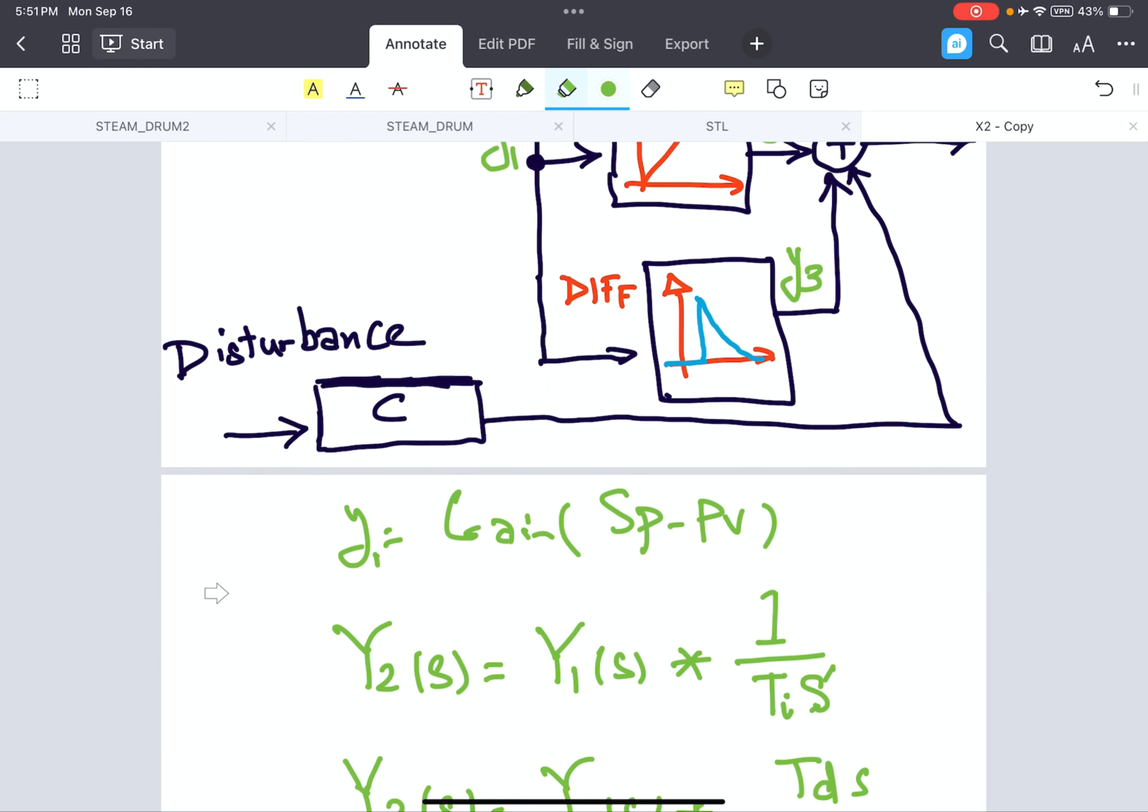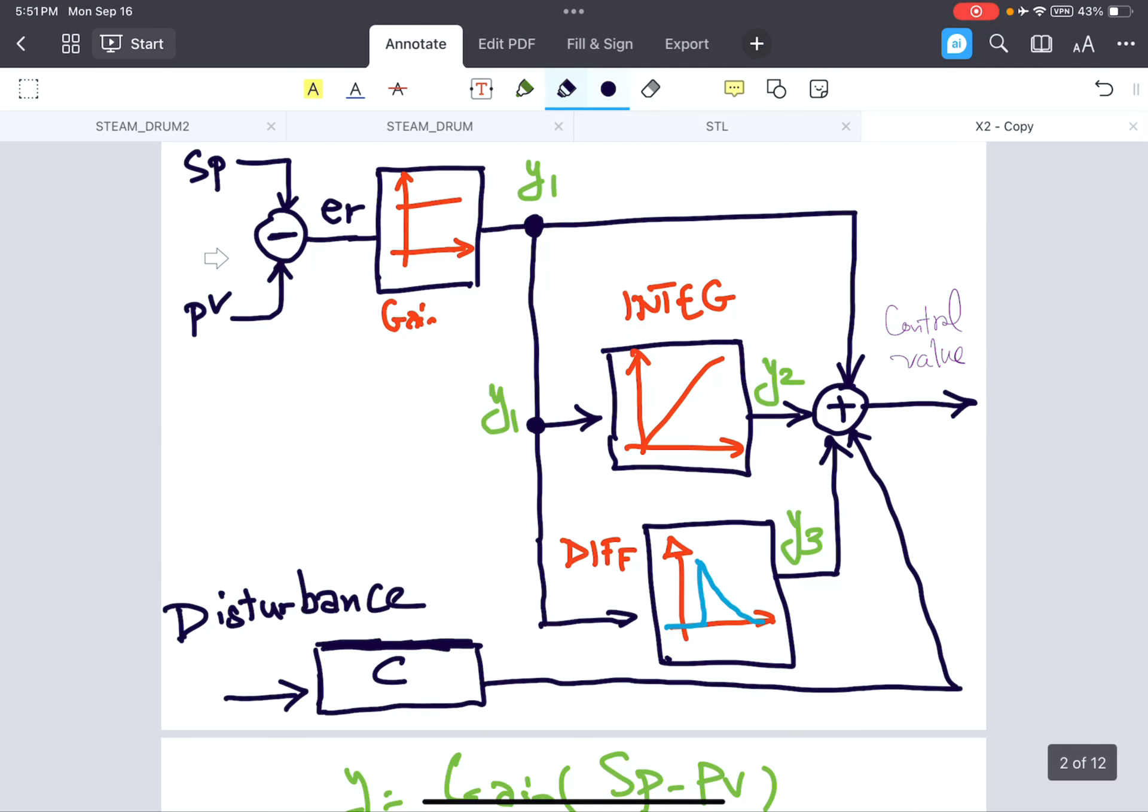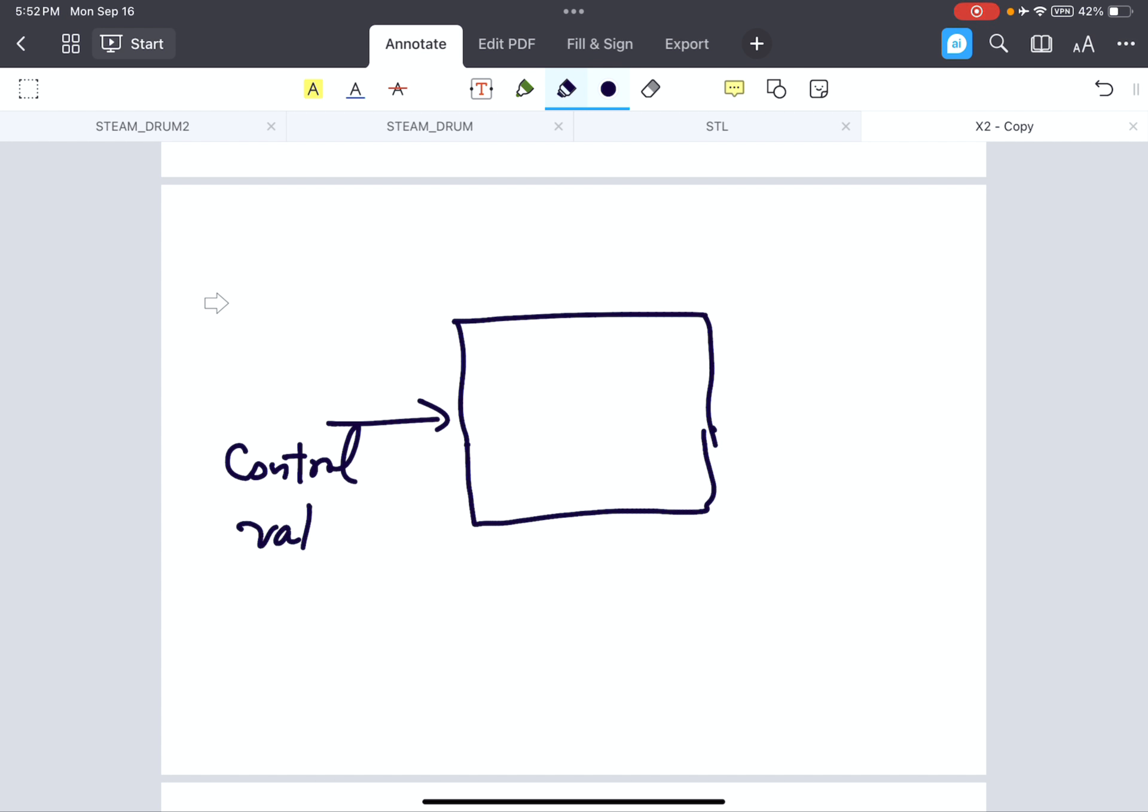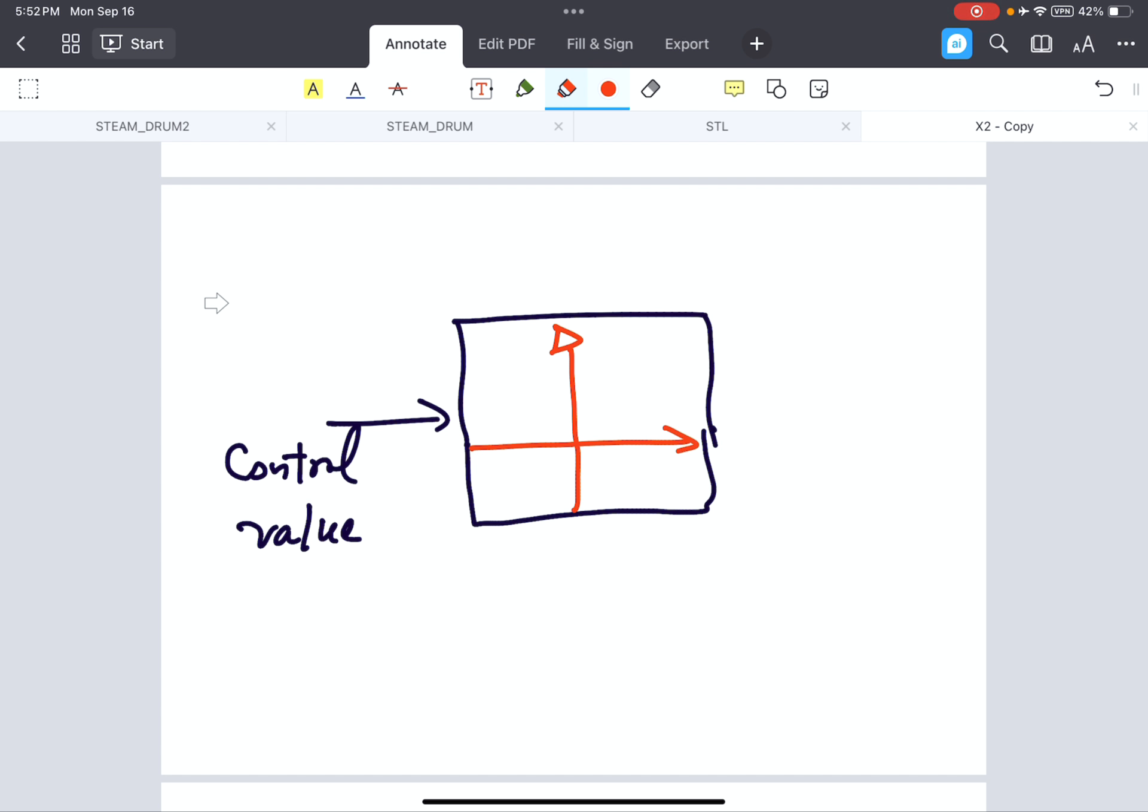Normally the control value, when we calculate the control value, the control value is fed to the limiter block. So we have in the final step the control value normally is fed into a limiter block like hard limiter, and here we limit the output to the two, to maximum values and the minimum value. The max is Lmn high and Lmn low.